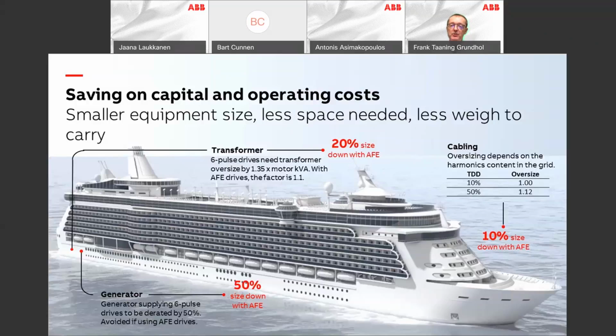Same goes for transformers. It's a 20% size reduction. And for your generators, it's actually almost 50% size down. Not because of the heating, but because standard drive technology has a negative impact on the voltage regulators in the generators. Therefore, active front-end drives are preferable because that allows you to use smaller generators and load them more fully, and thereby leverage your investment in the generation more effectively.